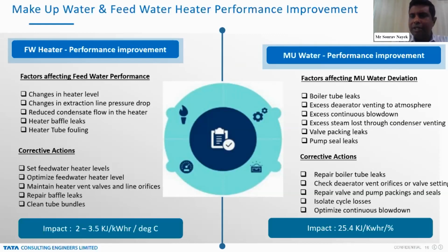The makeup water deviation is another factor which will cause deterioration of the heat rate. The aspects of the makeup water deviation are boiler tube leaks, deaerator venting to atmosphere, excess continuous blowdown from the boiler drum, excess steam loss through condenser venting, valve packing leaks, and different pump seal leaks, which also cause excess makeup in the cycle. Because as the losses or blowdown increase, the makeup quantity has to be increased to maintain the overall cycle mass flow. So when we increase the mass flow of the makeup water, this will increase the heat rate of the cycle.